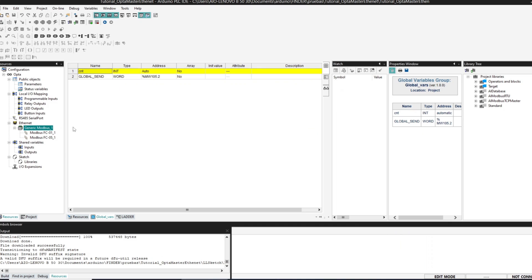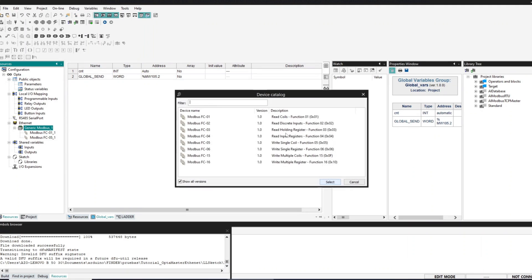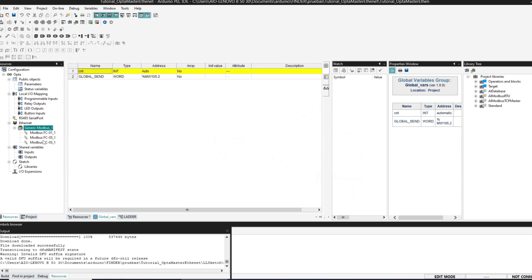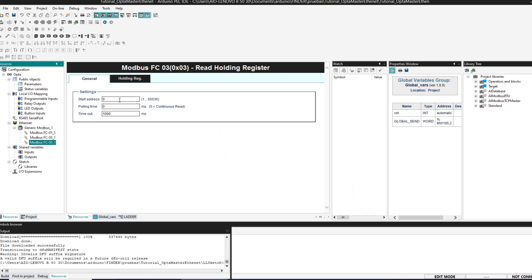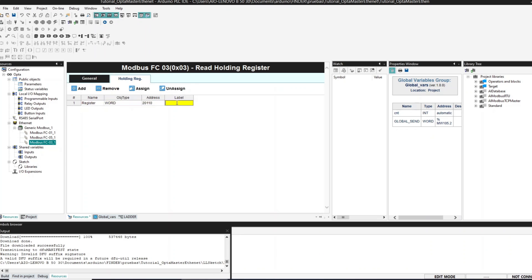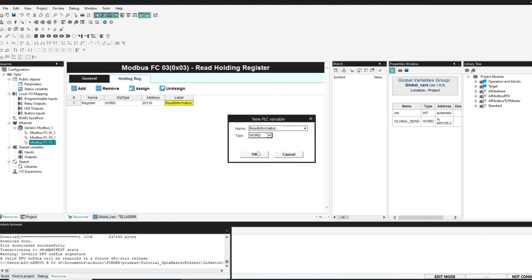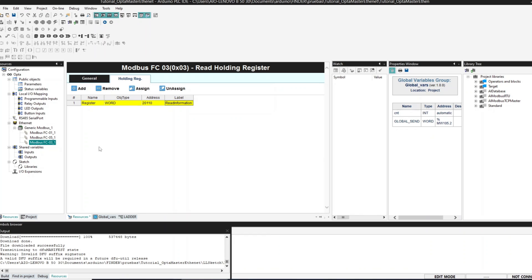We will now read and write integers. For that we are going to add a read holding register function. We must enter the address of the register that we are going to read — we are going to choose address 20110, polled each half a second. We create a new variable to store the info that we read, called 'read information'. We are going to read the number stored in this register, add a value to it, and then send it back to the slave.